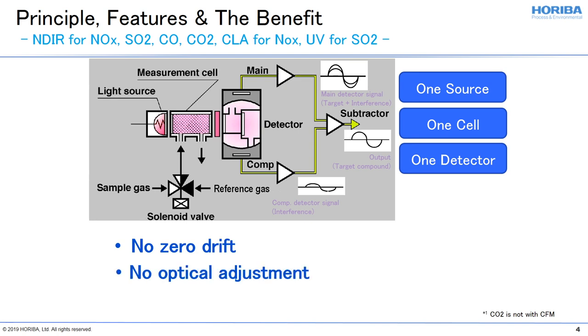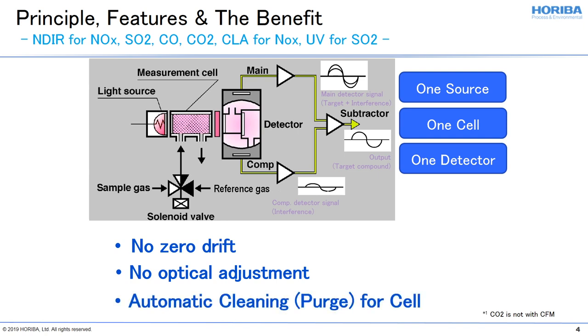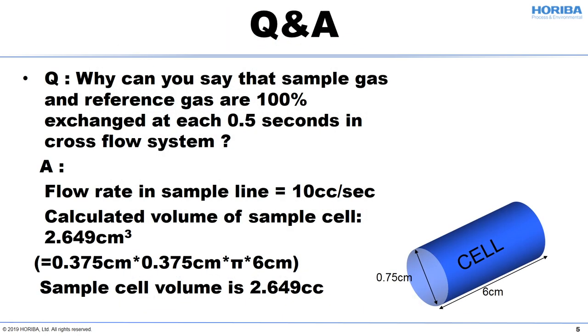Also, the reference gas can be dry ambient air. Each half second, air purges the sample cell to eliminate accumulation of dirt. As a result, this provides a longer life cycle, durability, and stable measurements. Contamination is not a problem.